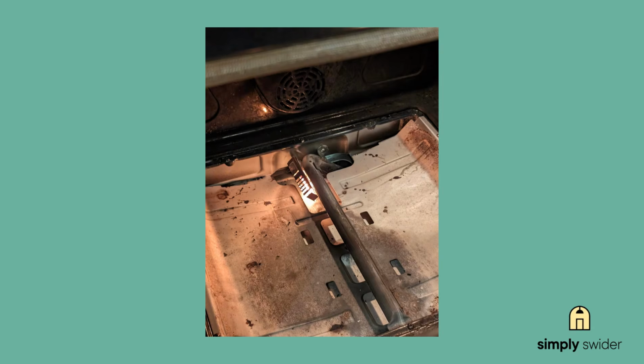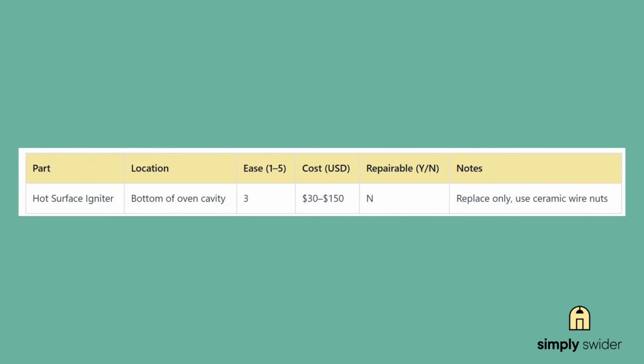Think of them like brake pads or light bulbs. They last about 3 to 7 years, then the ceramic material starts breaking down from all that thermal stress. Here's where most people mess up. They see that orange glow and think the igniter's fine, so they start replacing gas valves and control boards. Don't do that. You're throwing money away. The real test is amperage, not glow.